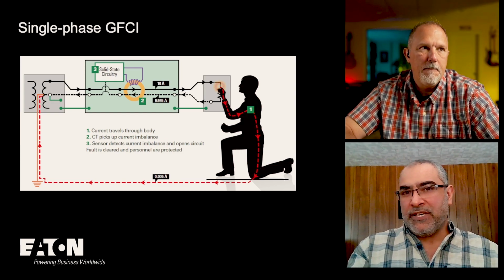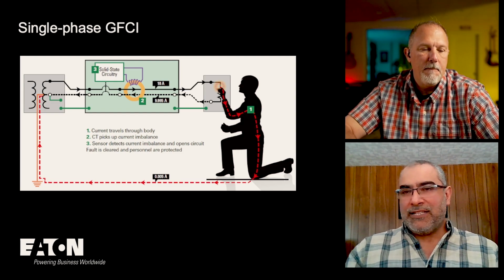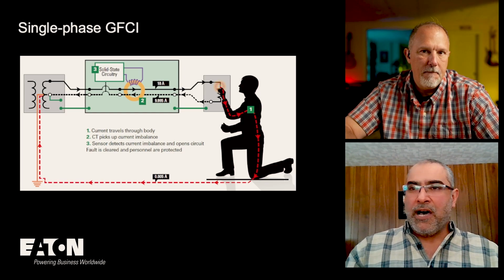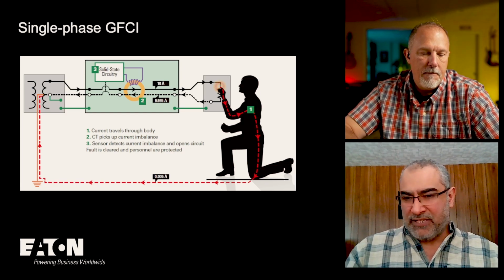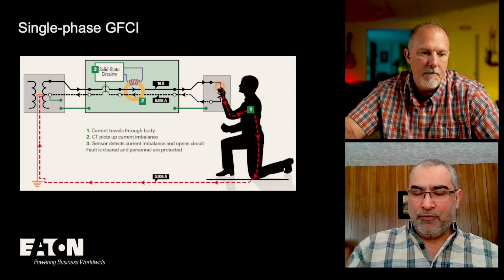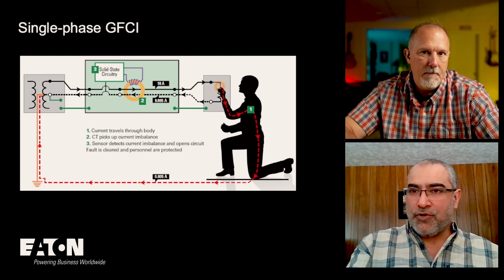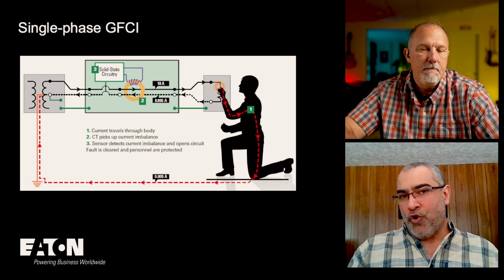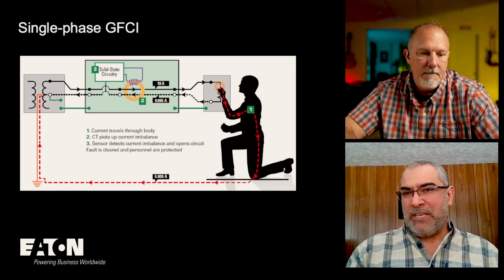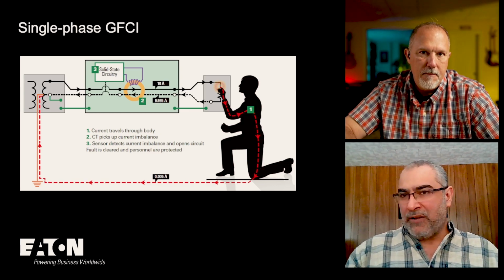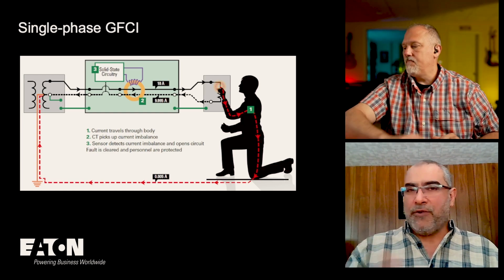So 500 ohms is very conservative, and it's better when we're testing, because the higher the impedance or resistance of the body, the more it limits the current - so it's safer. UL goes with a conservative number, 500 ohms. But again, that doesn't mean 500 ohms is the minimum you can ever get, because we're testing in a lab.